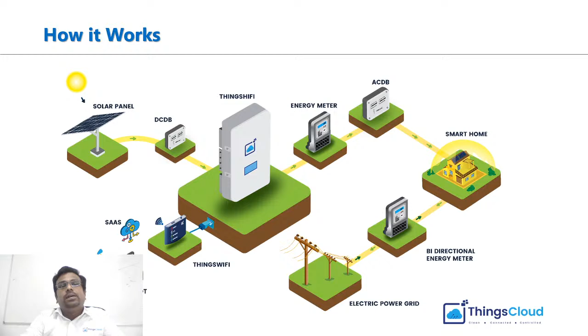Here there is a solar panel, so this will be based on the inverter capacity. If it is a 1 kilowatt system, there will be a maximum of 1200 watts, and if it is a 3 kilowatt, so maximum 3000 watts panel can be connected, and it will be connected through DC-DB to the inverter. So here there will be an SPD and breakers for safety purposes, and here it will convert DC to AC and feed to the grid.